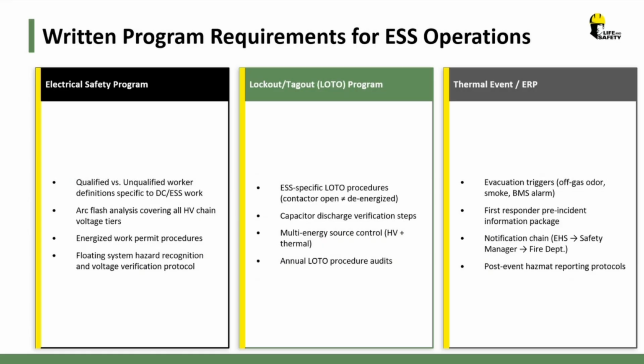Looking at the written program requirement, ESP, that's the electrical safety program. Every factory should have one of these. This is how you work on live voltage. This also includes your lockout tagout program. But the ESP is the document that defines what your live work permit looks like.